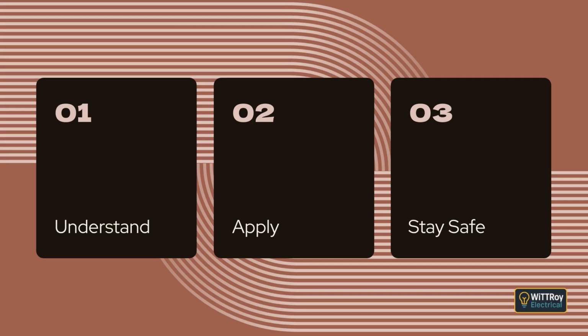Responsibility for determining whether an area is hazardous rests with the people in control of the installation. Hazardous areas are defined using the requirements of ASNZS 60079.10.1 for gas or vapor, and ASNZS 60079.10.2 for combustible dust. Clause 7.7.2.2 Recognized hazardous areas. Two main types of hazardous areas are recognized.